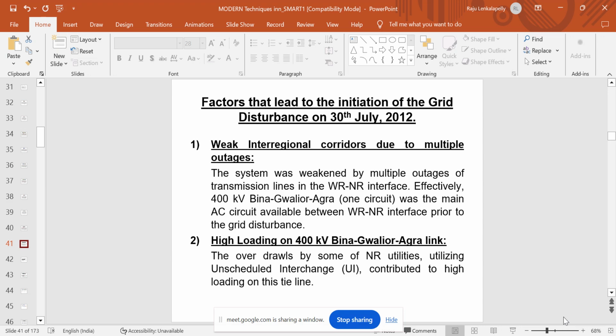Also, consider the 400 kV Bina-Gwalior-Agra line, which is a double circuit line. One circuit was already out. Normally, when both circuits of a double circuit line are healthy, power transfers 50-50 between them. But when a disturbance occurs and one line trips, 100% of the power transfers through the single remaining line. This had already happened, leading to high loading on the 400 kV Bina-Gwalior-Agra link.